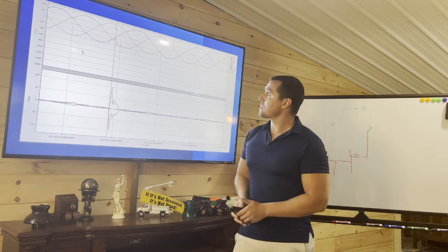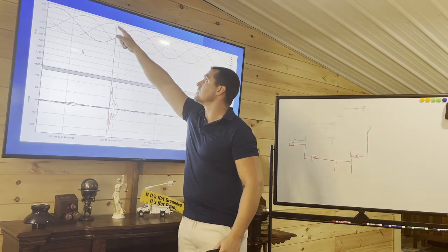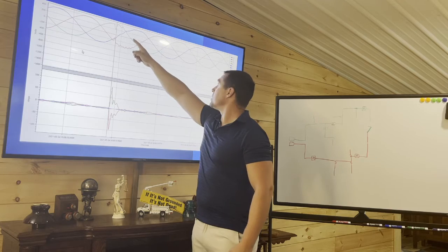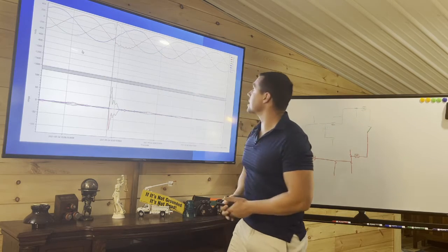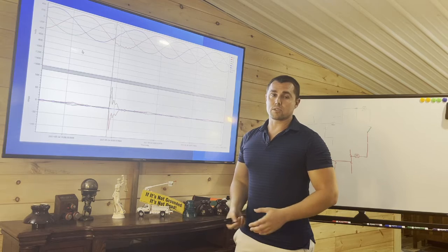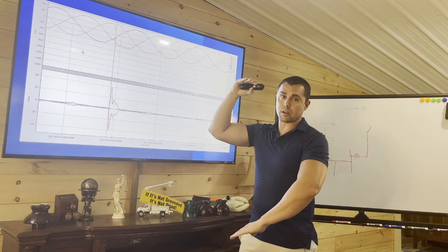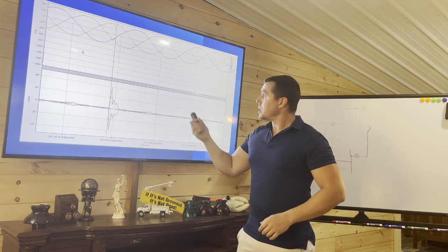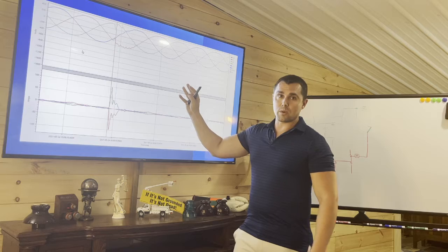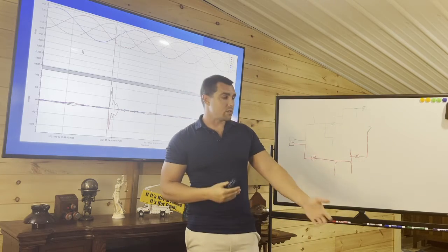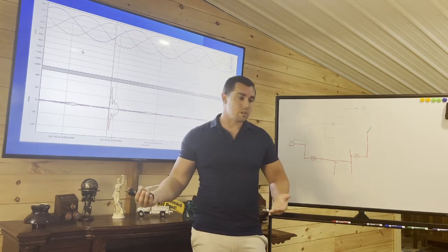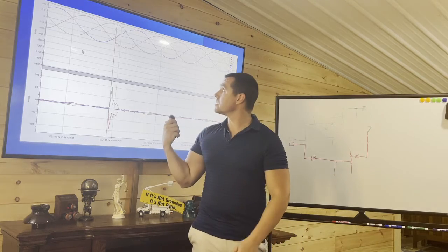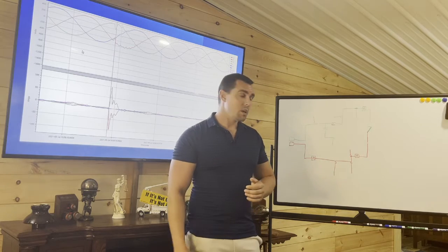Well, this doesn't happen. The open and close, you can see here, this was almost at the peak of the positive flux on B phase, and so with A phase. Now that is what causes the distortion, depending on how high or negative the flux is when it opens and closes. Now you'll see similar distortion, maybe not a ring wave or such, but you see distortion and faults caused by utility operations, your LTCs, your regulator banks, everything causes sinusoidal distortion.